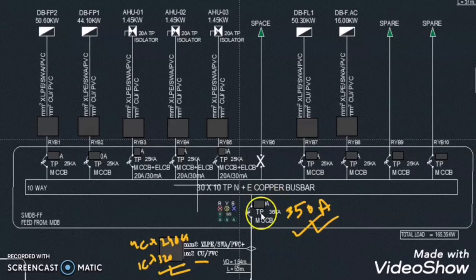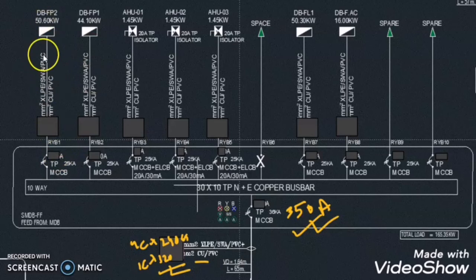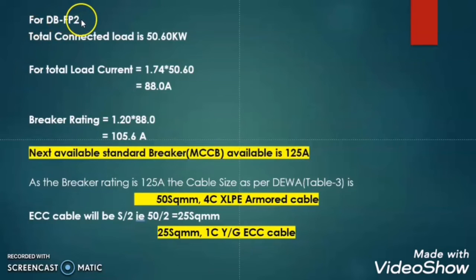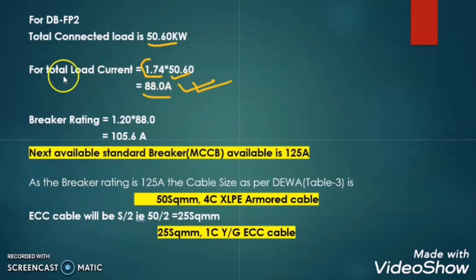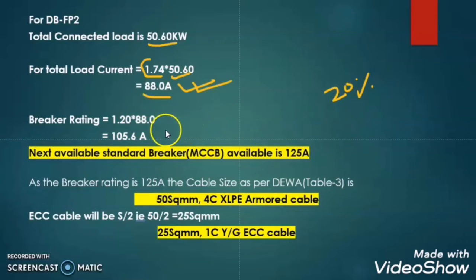So far we have calculated the main incoming breaker and the main incoming cable of this SMDB. Now let us calculate the outgoing breaker and cable required for this load. The load for DBFP2 is 50.60 kW. So the total load current is 1.74 × 50.60 = 88 Ampere. Now in order to calculate the breaker rating we have to multiply with the safety margin. I consider here 20% as the safety margin, so multiplying by 1.20 gives 105.6 Ampere.